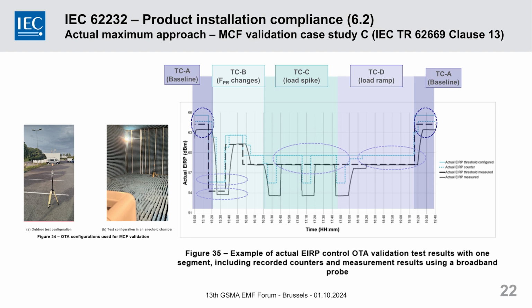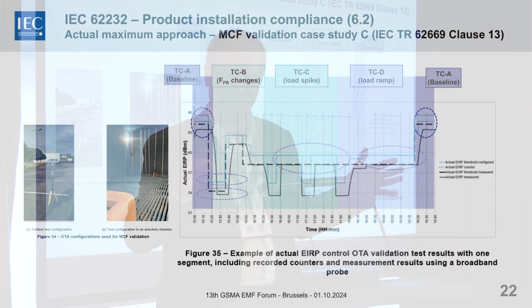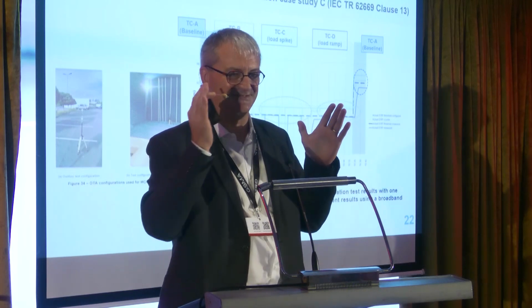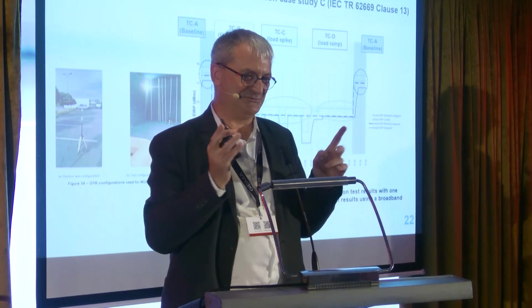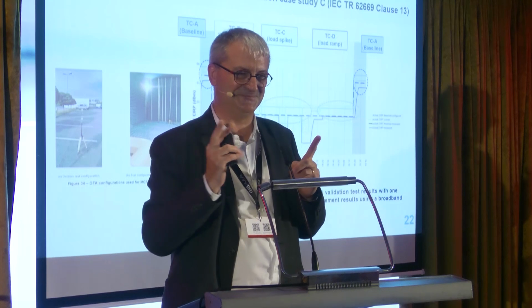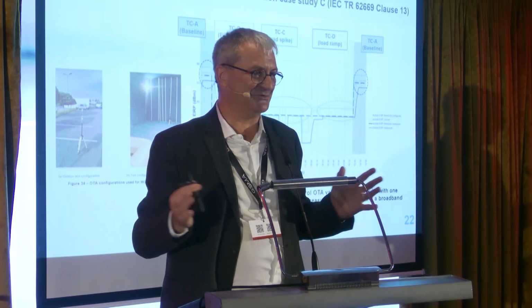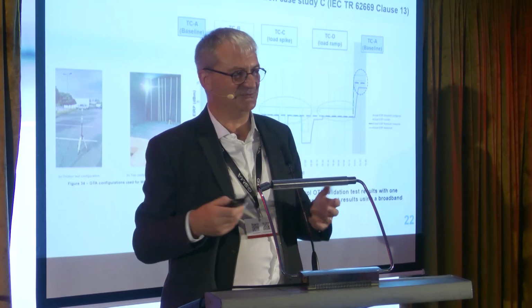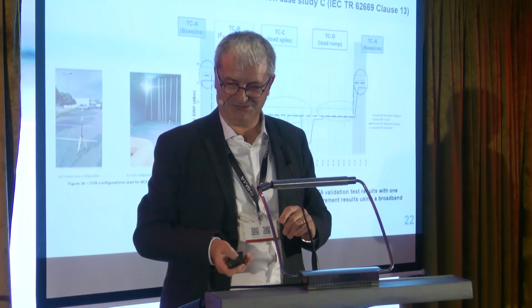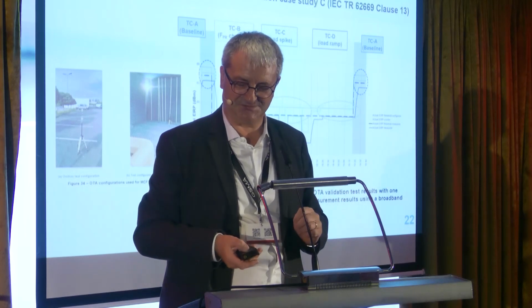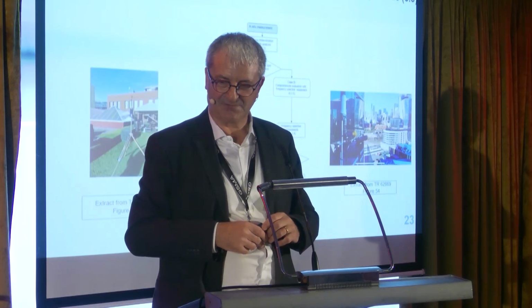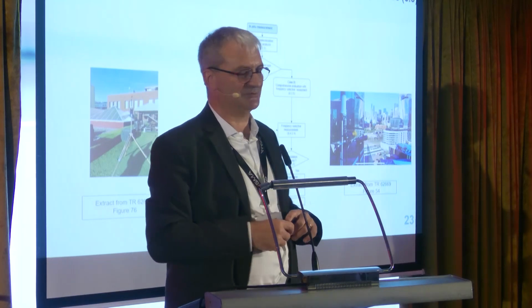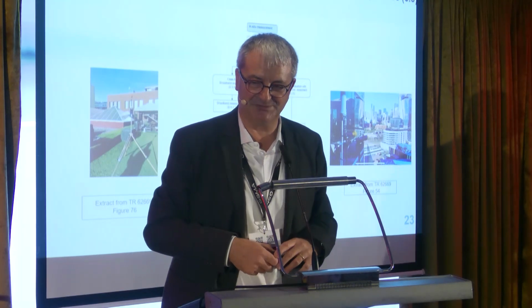As an example, this test is taking 5 hours because of the 6-minute averaging time and the fact that at each step we need to wait 3 times the averaging time for stability. The overall process takes a few hours, and we are suggesting to discuss this in the committee, how to optimize this part. So this concludes product installation compliance, and now we move to the measurement part.